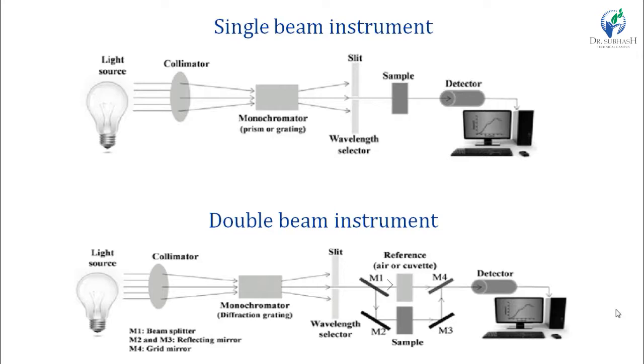Beam means radiation beam. In a single beam instrument, there is one sample holder — just the sample. In a double beam instrument, two sample holders are present: first is reference and second is sample. Reference means the standard of our sample. For example, if working with a paracetamol tablet, the pure standard powder of paracetamol with 95% purity is known as the reference.